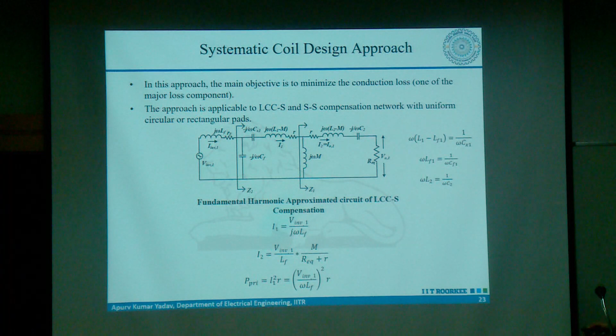We define the power loss in the primary coil as I1 square into R, where R is the resistance of the coil, obtained in this form. Then we write down similarly for secondary side power loss, and then we define the loss factor, which is the ratio of the power losses in the primary and secondary coil divided by the total output power which we are getting.